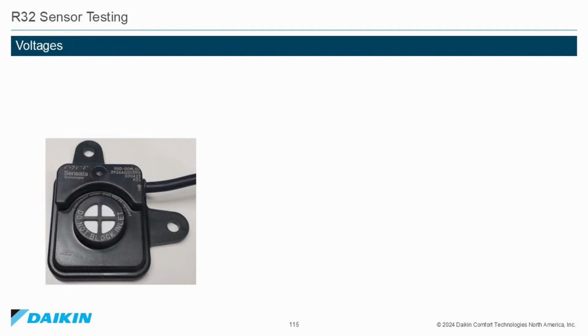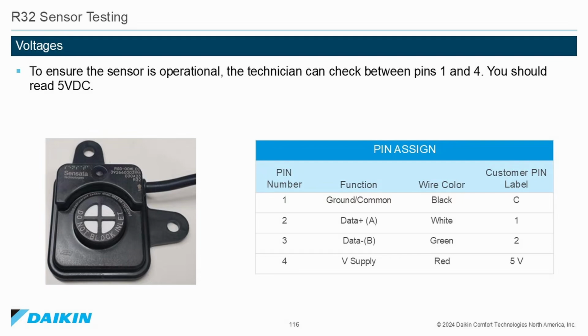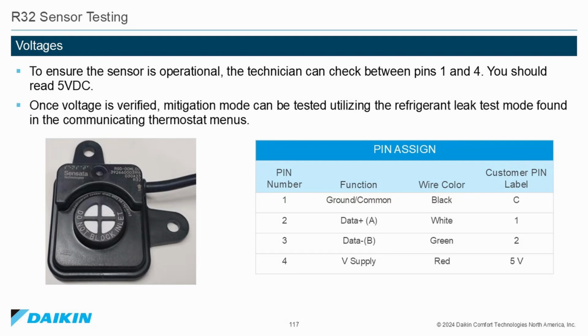R32 sensor testing. Voltages. To ensure the sensor is operational, the technician can check between pins 1 and 4. You should read 5 volts DC. Pins 2 and 3 are data communications. Once the voltage is verified, mitigation mode can be tested utilizing the refrigerant leak test mode that's found in the communicating thermostat menus.